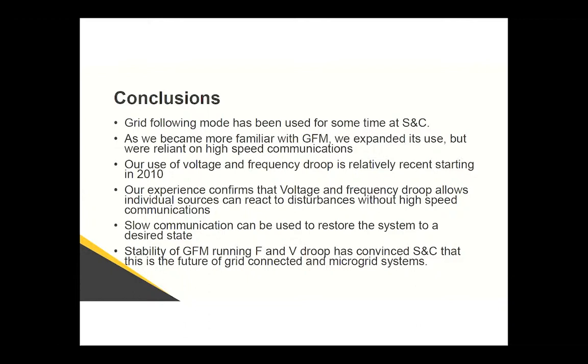What it really comes down to is most grid forming inverters need to have some overload, where the grid following don't necessarily have to have the overload. But if you look at the same capability in the steady state, they're basically the same cost, as we found. Now, if you need overload, you can get overload that isn't steady state at a lower cost than steady state overload. So it depends on how much overload you need.